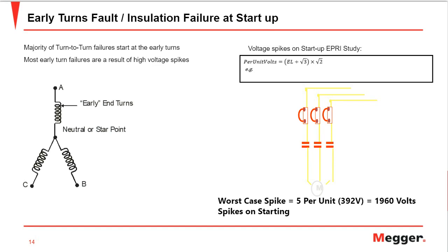And coming back to early turns faults, the majority of turn failures start at the early turns, because these are the turns which face most of the voltage gradient or most of the voltage spikes because of the position of those turns. We'll see how the voltage is distributed across the motor coils.